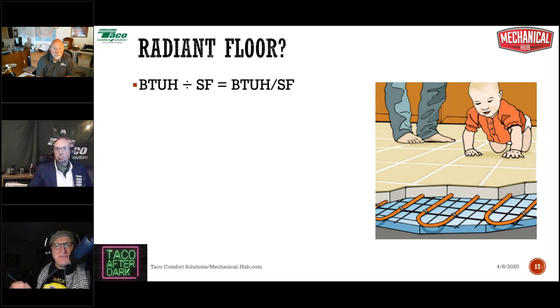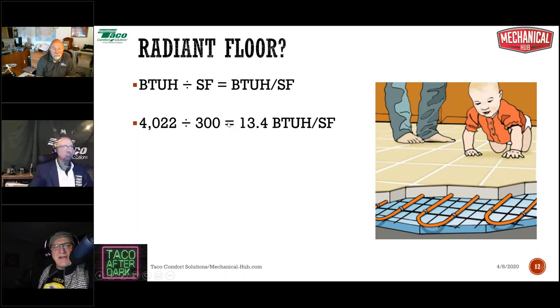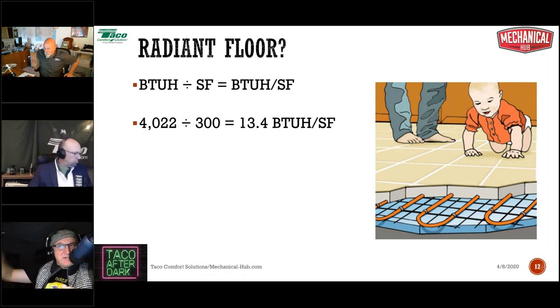But for our purposes, it's just a 15 by 20 foot room, a 300 square foot room. That's the number we're going to use. So in our example, the BTU load is 4,022 divided by the 300 square feet. That gives us a BTU per square foot load of 13.4. In our example, our outdoor design condition was 0 degrees. Under 0 degree temperatures, I need to get 13.4 BTUs per square foot out of that floor.